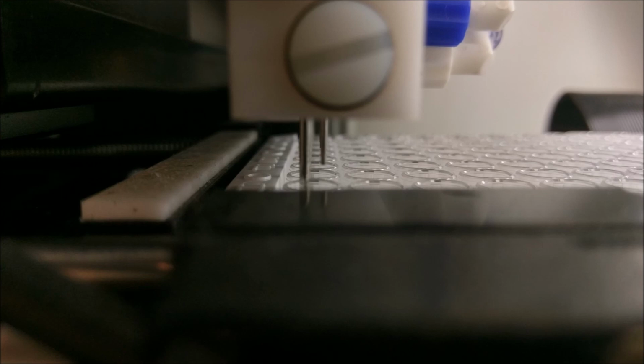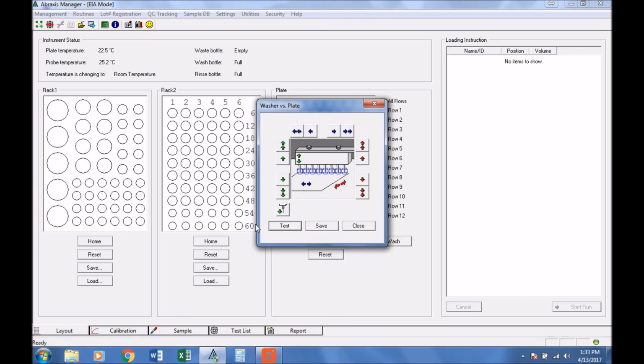From this still camera shot, the user can see that the dispensing probe, the shorter probe, and the aspirating probe, the longer probe, are the same distance away from either side of the wells, and the space between these probes is directly in the center. When satisfied, click Save, then Close.